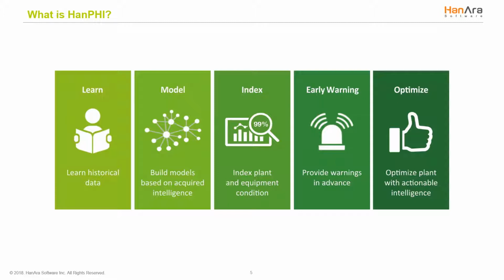Here, the variables are read, and the model executor then calculates the expected values, residuals, and health index of each process variable, piece of equipment, and the entire plant. But information isn't useful unless it's easily accessible and understandable. So the solution displays the health index in an intuitive hierarchical order to help focus the user on the root cause variable. And if the solution detects an anomaly, an early warning is generated.